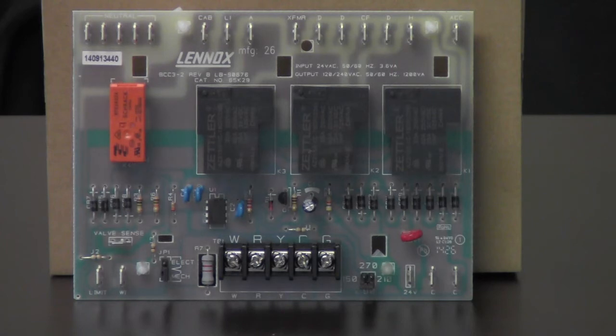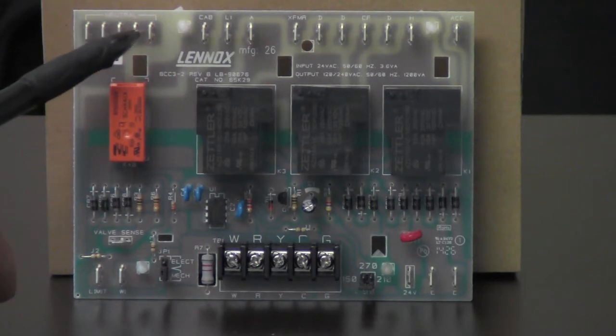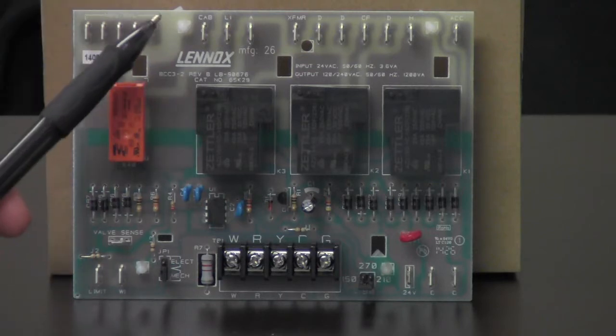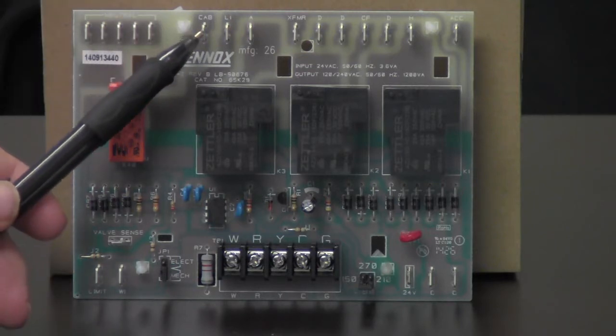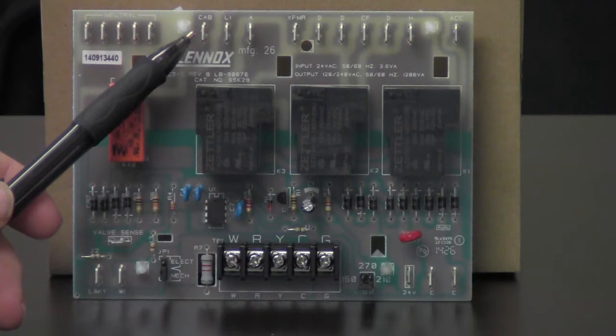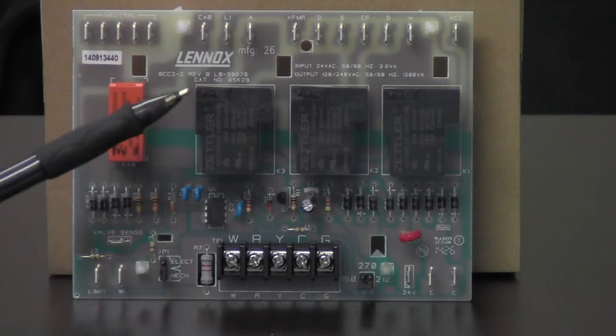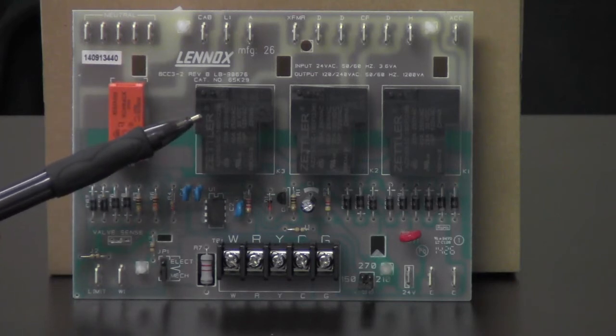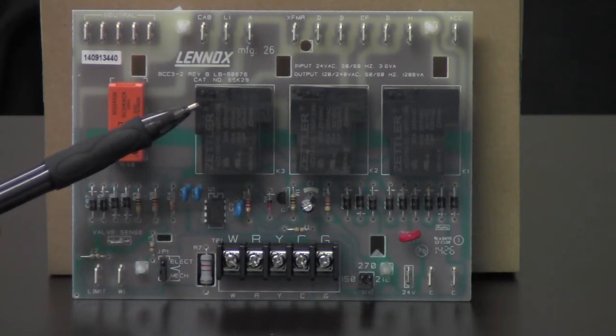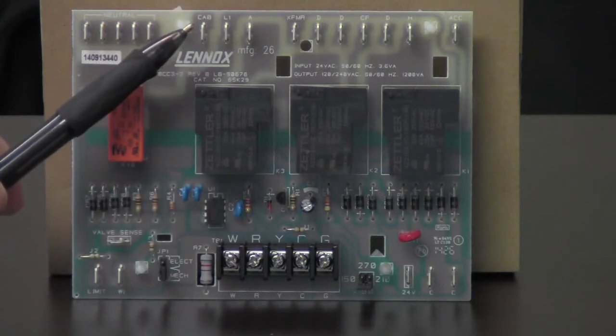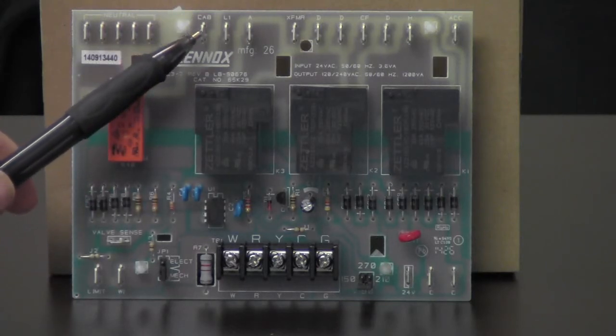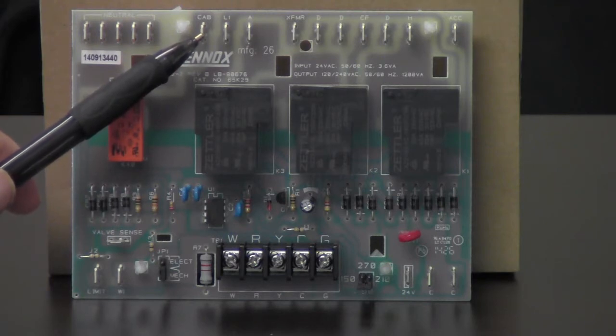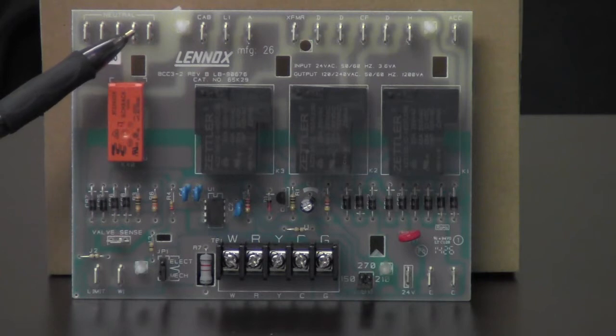So let's get started with our line voltage. We have these five connectors up here that are all going to be our neutral wires. Next right here it says CAB, that stands for combustion air blower. A lot of times these blower controls are on a G23 or G20. Now the G20 doesn't have a combustion air blower, it has a damper. So this is where we'll hook up our damper motor. The hot side of the damper motor will hook up here, and the other side will go to one of our neutrals.